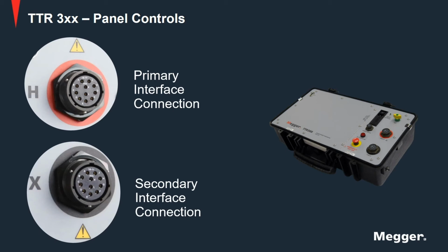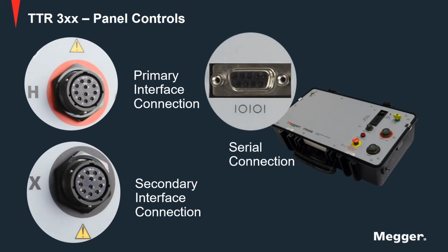This connection has all the interfaces required to connect current and voltage inputs from the secondary or tertiary winding of a transformer into the TTR300 unit. Next is the serial connection. This connection allows for PC control of the TTR300 using PowerDB software.